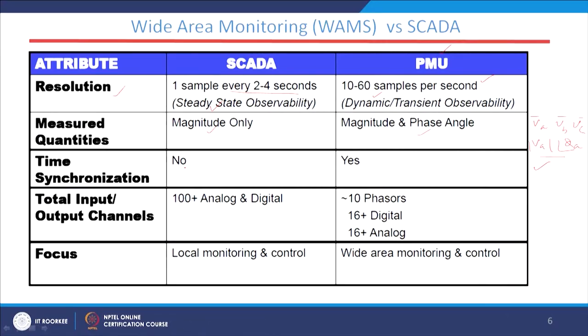Inside the PMU there is a signal processing algorithm called DFT — Discrete Fourier Transform — using which we can calculate the phasors of different signals like voltage and current. As far as time synchronization is concerned, synchronization is absent in SCADA. If voltage is measured at two different buses at different times, we need to bring them to a common time frame to compare them, and that synchronization is missing in SCADA. However, in case of PMU this synchronization is present, and we can compare bus voltages and angles at a common time frame, aided by the GPS satellite.